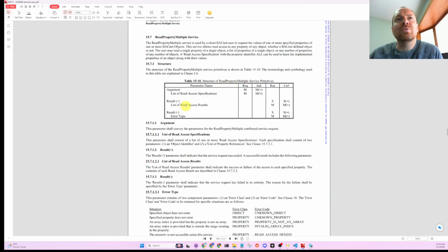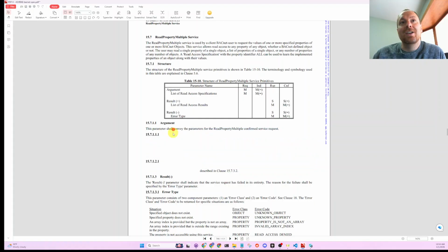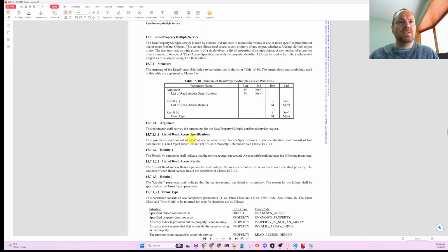I've run into some issues with the BACnet read multiple in BACpypes on some BACnet gateway. I can't even remember the device. It might have been a lighting control system. It had like 4,000 points in it. And I think I noticed in BACpypes that there is no chunking built into the Python backend. So if I requested 2,000 points, which I can write a Python script to do, but the device says no, I can't do that.